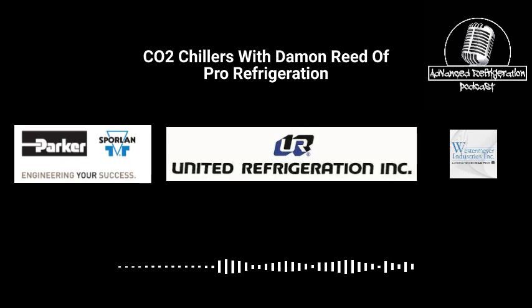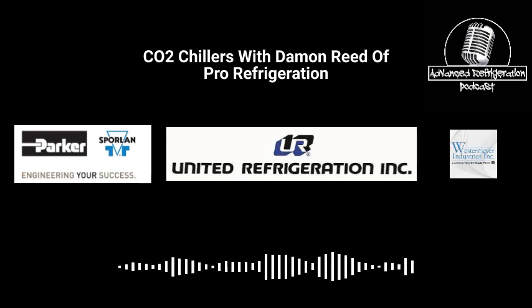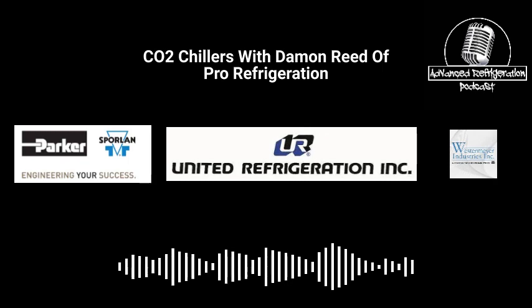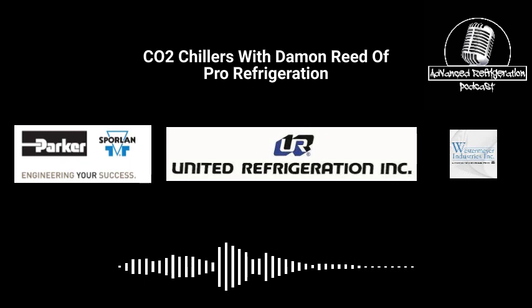Yeah. So storage reservoirs, and that's where you learn more. Initially, when we did the design and development, it was, what is our maximum heat recovery potential that we could get off of this piece of equipment? So our refrigeration load in BTUs per hour was steady. I have a steady BTU per hour cooling load that this facility is going to deliver. Cows are always milking. That's right. So I've got steady BTUs per hour I'm working with. Now factoring in total heat of rejection, ambience, things like that.